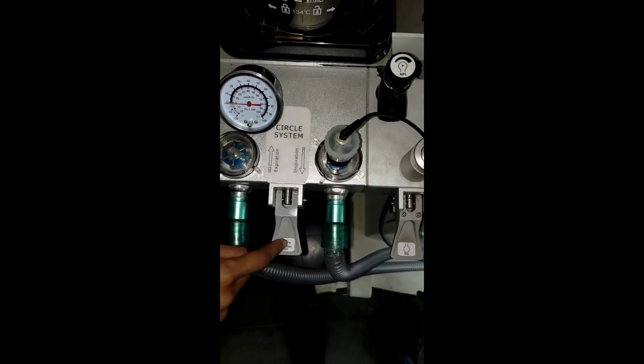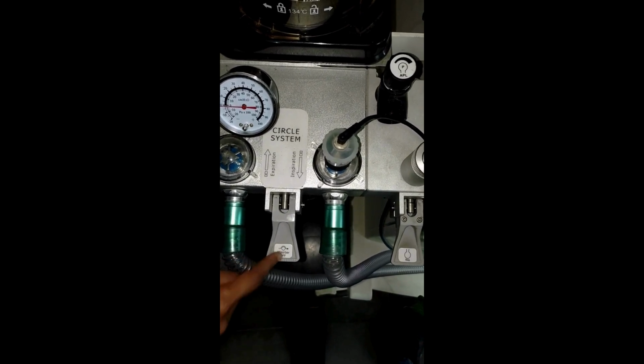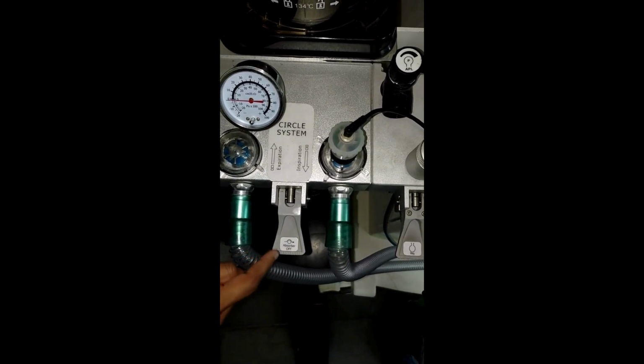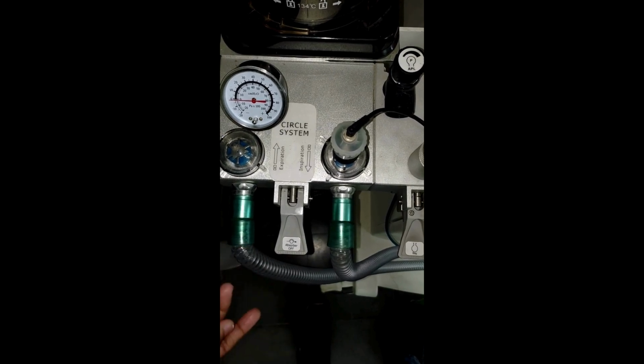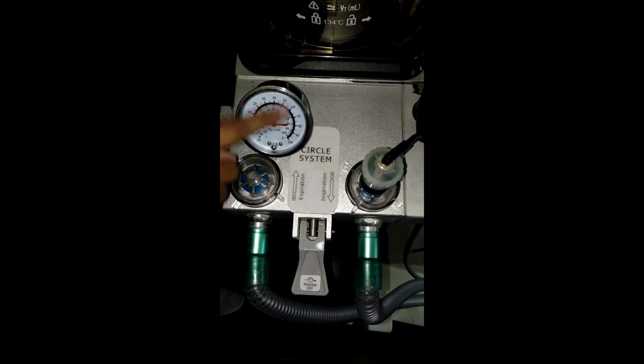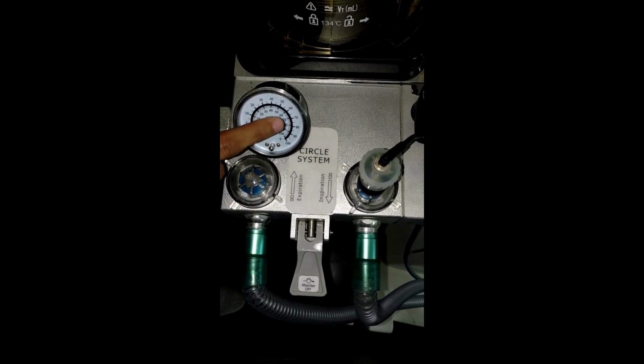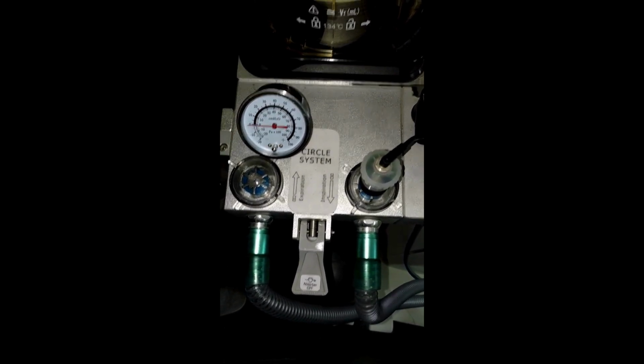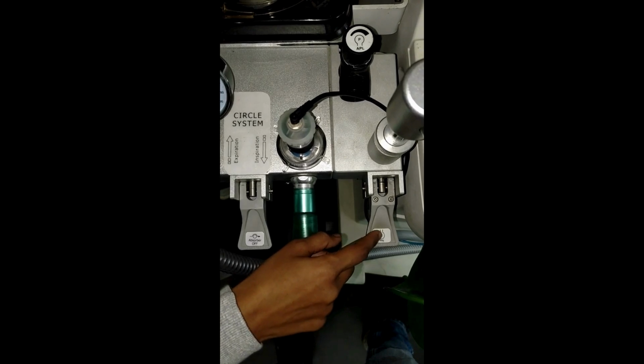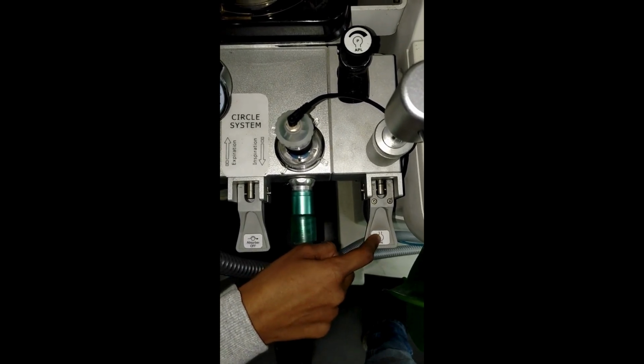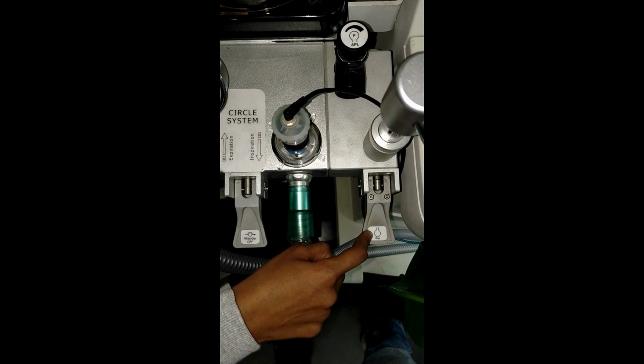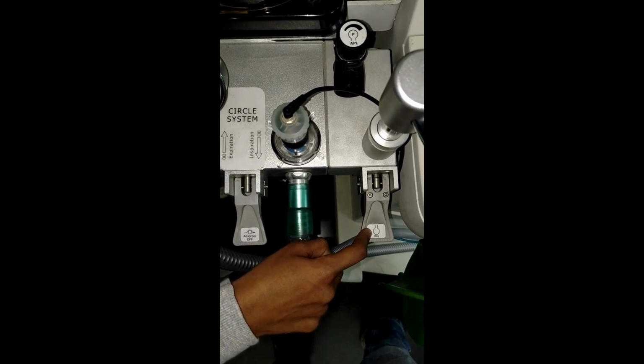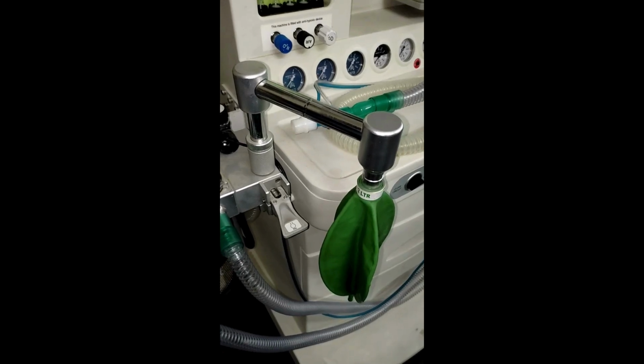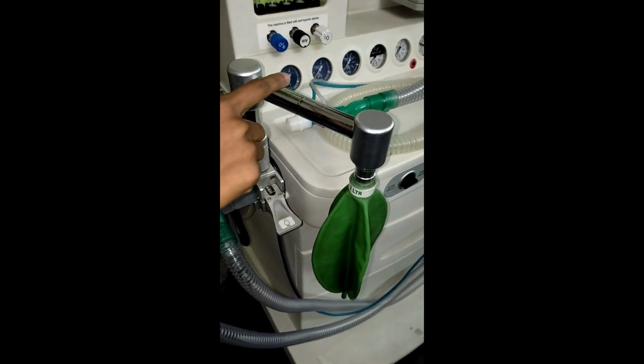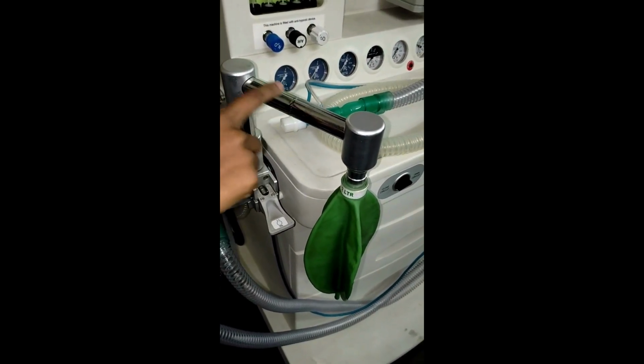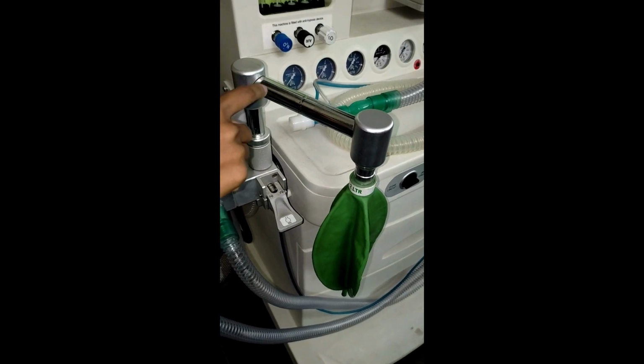The bypass switch in the circle absorber is used for bypassing the circle absorber from the patient circuit for changing the soda lime during an ongoing procedure. Manometer shows the reading of the pressure exerted on the lungs of the patient. Back to ventilator changeover switch. This switch is used to change the driving of the machine from manual breathing back to the ventilator. Bag arm is present in the circle absorber for mounting the breathing bag when the ventilation is done manually with the help of the breathing bag.